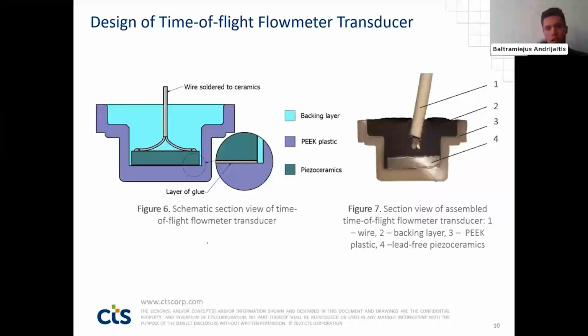Now let's dive into our investigated case and the design of the flow meter transducer. At first glance, the flow meter design looks quite simple. We have casing material, which is purple, a piezoceramics, which is green, and a backing layer, which is blue, and a layer of glue. However, there are some challenges in designing and assembling the flow meter.